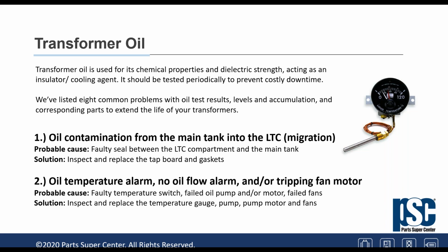And the second, transformer oil, confirms what I just said. Oil contamination from the main tank into the LTC by migration. Again, don't forget, the oil can go from one tank to another, but usually it goes from the main tank to the LTC compartment because the pressure in the main tank is much higher than in the LTC compartment, because of the high volume of oil in the main tank. But again, gas is funny; it can travel in either direction.